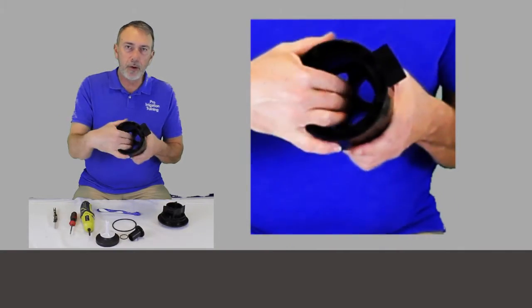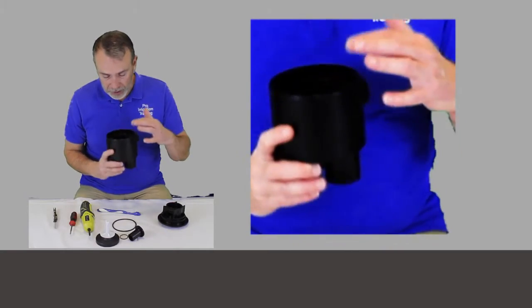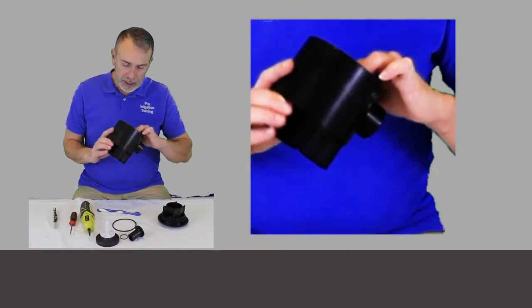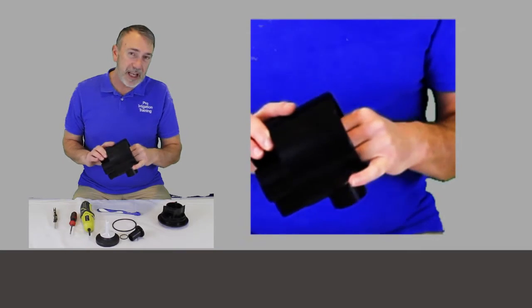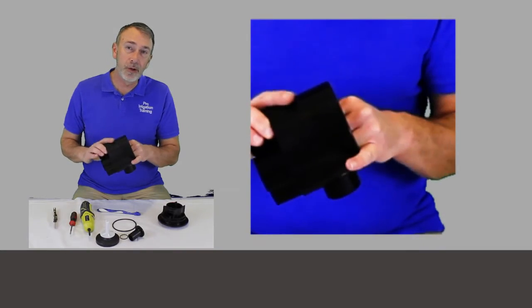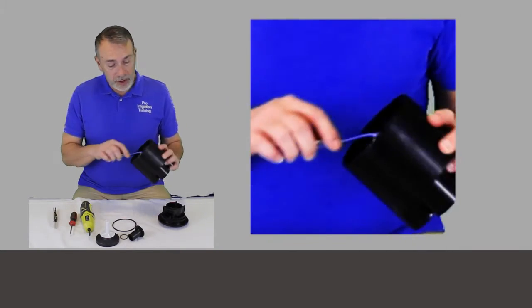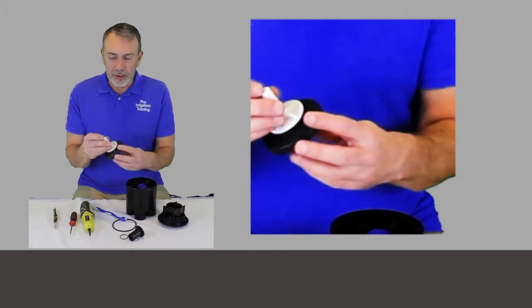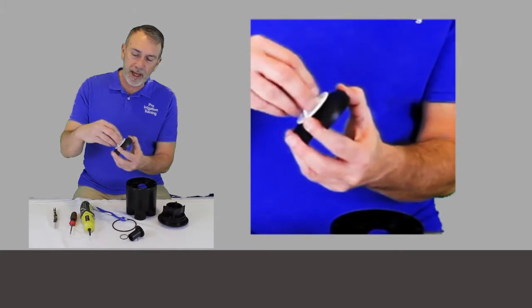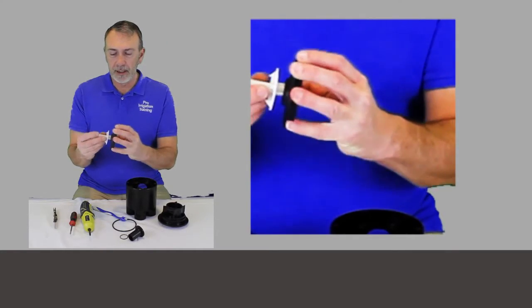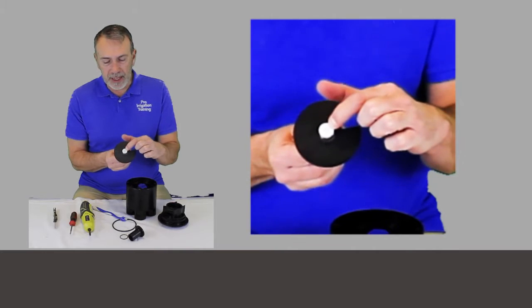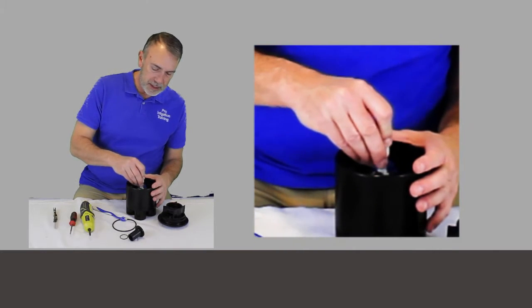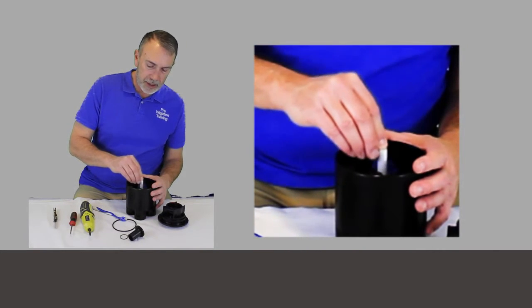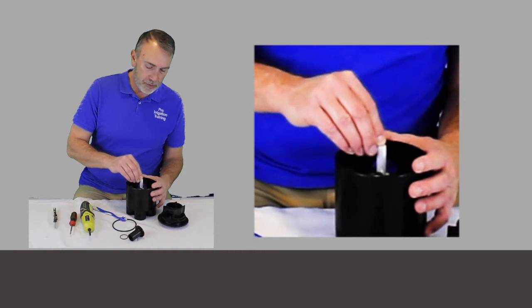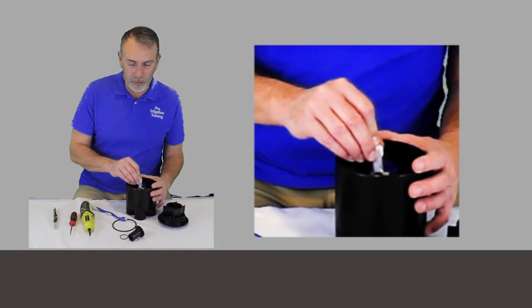But there's also a little post right here that you surely can't see in the video, but it's like a little 2-inch post here. And sometimes that post can get some scale and buildup on it. So that's something else you want to make sure is clean, flush it out. And then your stem, which is this white piece here, and this is the disc. The stem has a spring down inside the middle, and you want to set that on that post and make sure the spring is strong and it's bouncing back and forth on there.